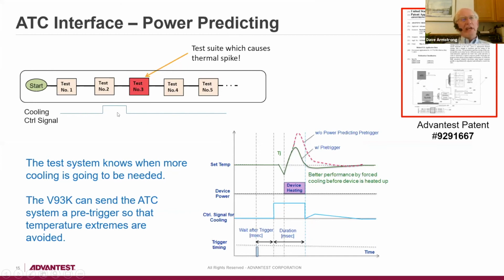I can change the target temperature on the fly because the tester knows when that test is starting, and it knows what the power profile is for that test, even if I'm not monitoring it myself. This allows me to tell the thermal system to cool down early, so the power transient is more of a plus or minus some degree C, not just a plus degree C. This keeps the device from overheating and from thermal runaway.